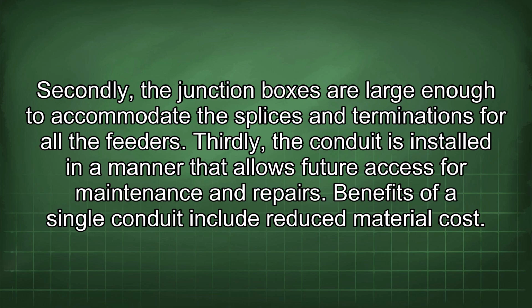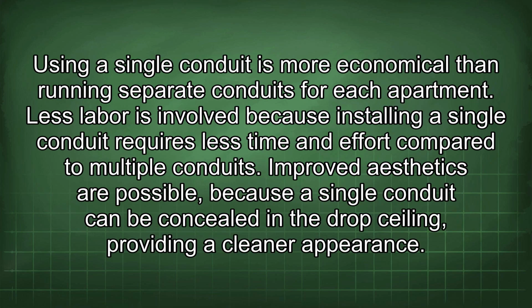Benefits of a single conduit include reduced material cost. Using a single conduit is more economical than running separate conduits for each apartment. Less labor is involved because installing a single conduit requires less time and effort compared to multiple conduits. Improved aesthetics are possible because a single conduit can be concealed in the drop ceiling, providing a cleaner appearance.